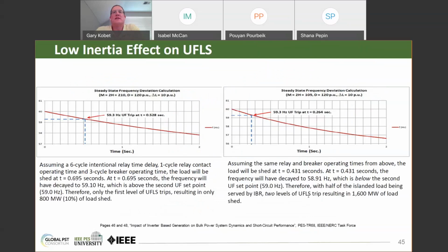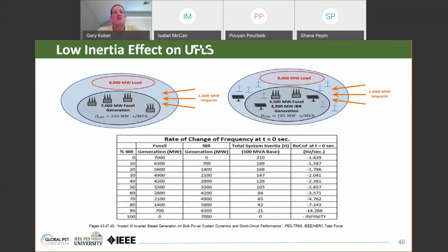So the rate of change of frequency is higher, and the results are that on the left, based on that rate of change of frequency, you may shed about 800 megawatts in this sample system, whereas on the right, when the rate of change of frequency is double, you stand to possibly shed additional load. And so the whole idea here is that under-frequency load shed schemes may have to be adjusted to account for this. And the next slide just has four different percentages in that same test system.